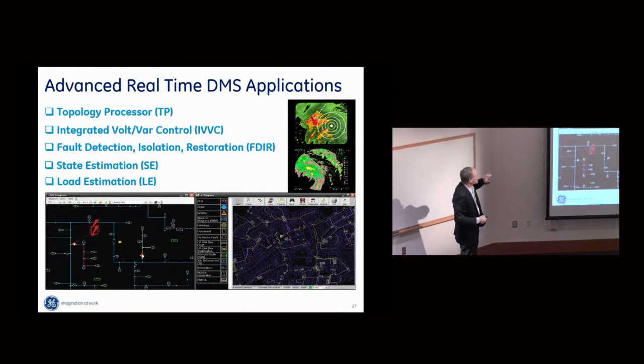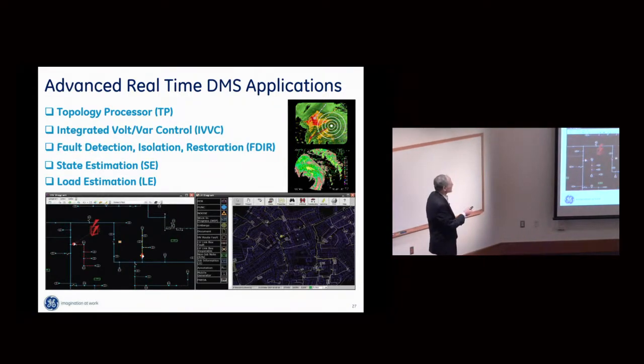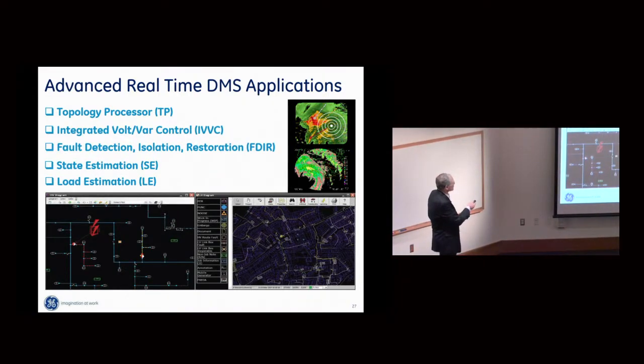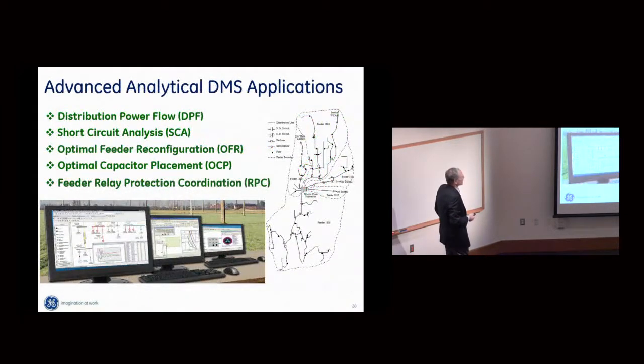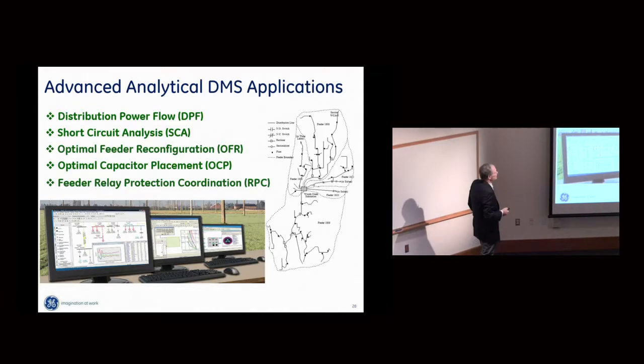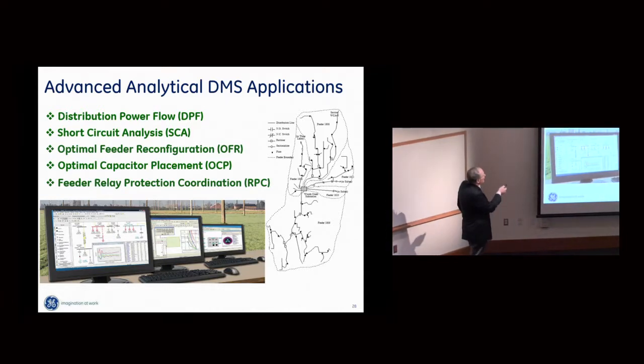But I like to think of applications in three different areas. One would be real time - these are online applications that dispatchers use: topology processing, volt/VAR control, fault detection, isolation, restoration, state estimator, and load estimation. The analytical applications I can do on demand. I classify this one as both on-demand and online, because as an operator I'd want a power flow tool I could use online.